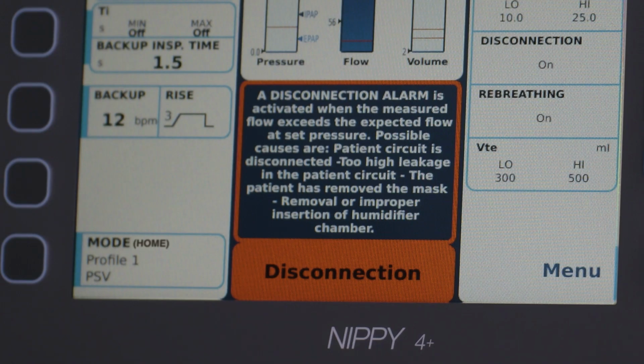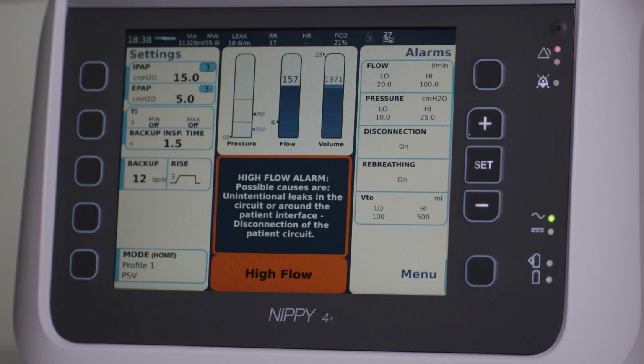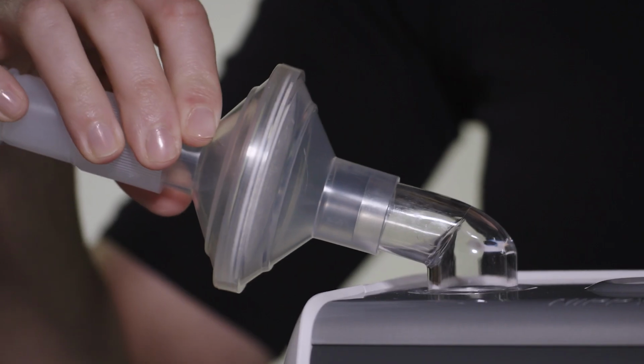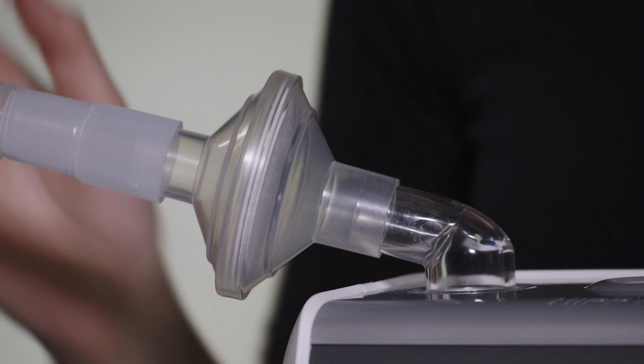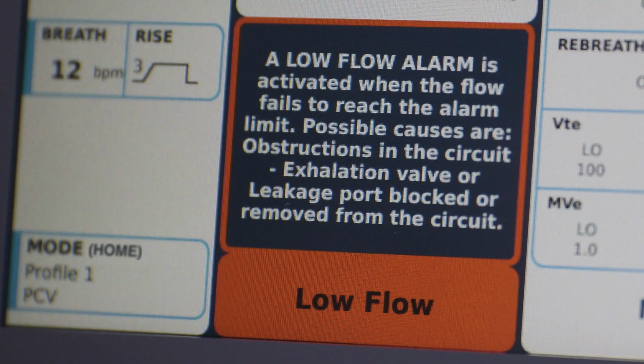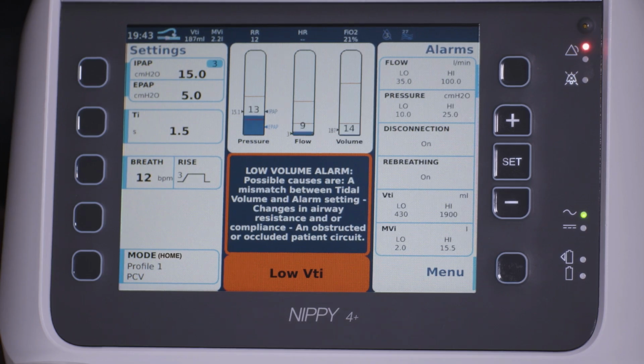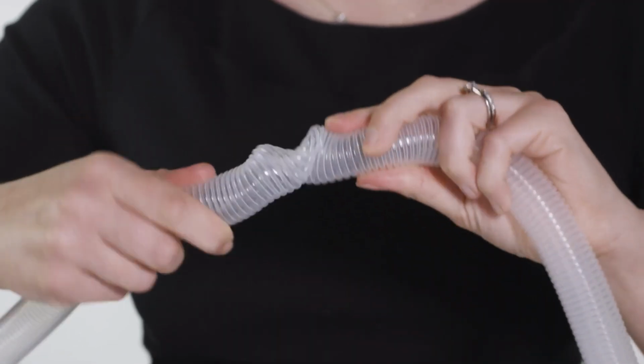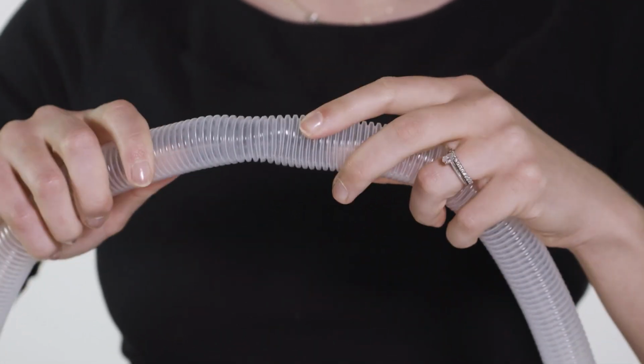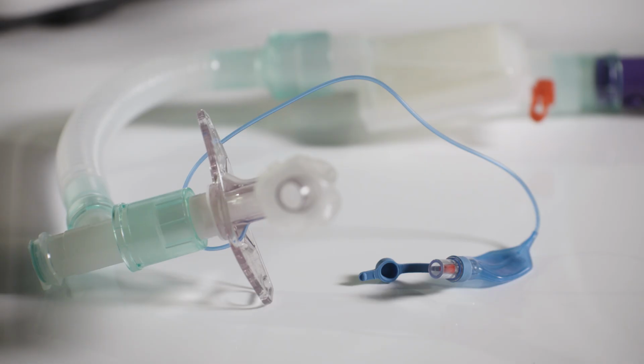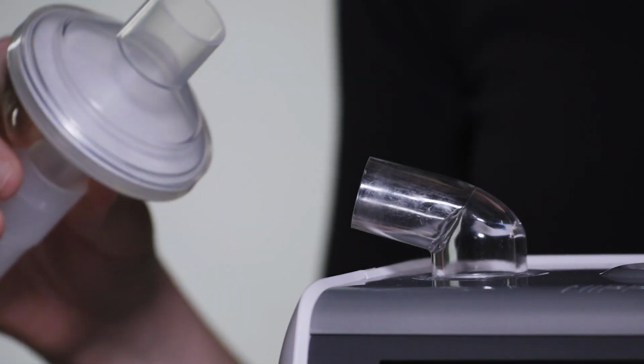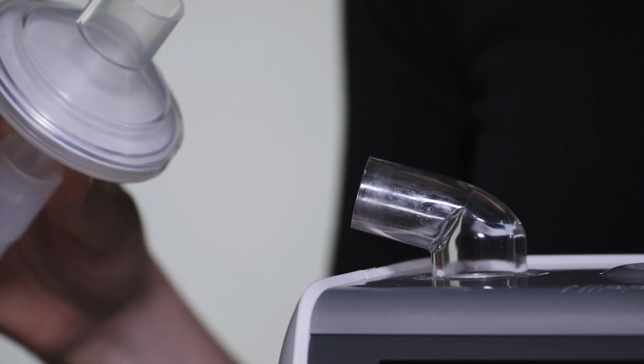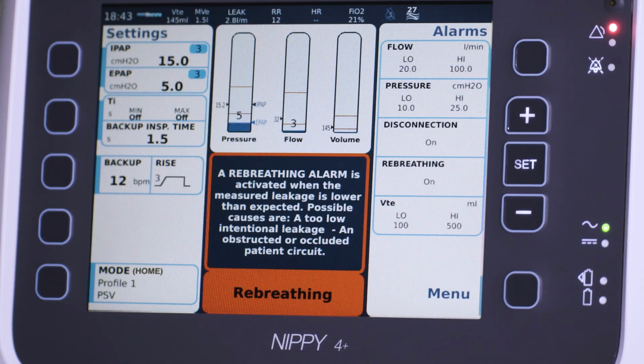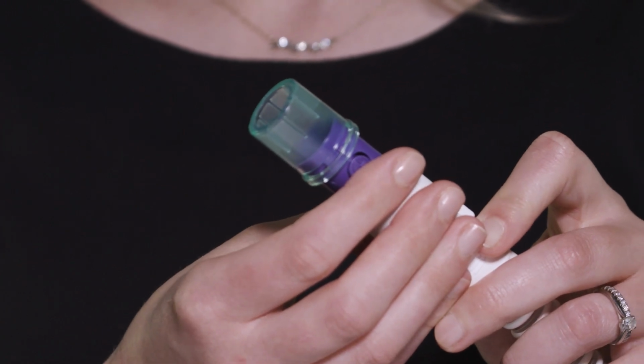A circuit disconnection alarm or high flow alarm may indicate a high circuit leak. Check the circuit is intact and connected to the device. A low flow or low volume alarm would suggest the airflow is limited. Check for any blockages or kinks in the circuit, or potentially secretions within the tracheostomy tube itself, and ensure any antibacterial filters in the circuit are clean. A rebreathing alarm may also indicate reduced leakage from the circuit, in which case you should inspect the leakage port.